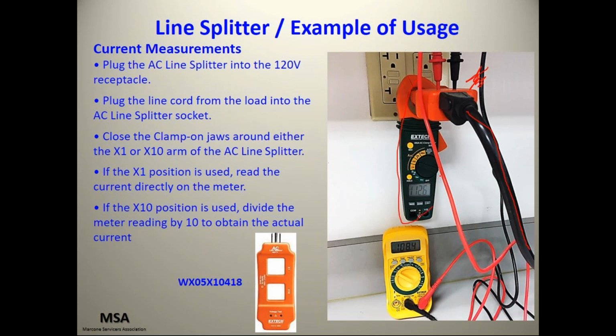Okay, they have the amp probe in the splitter. It says close the clamp-on jaws around either the X1 or the X10 arm of the AC line splitter. Okay, that's these openings here. If the X1 position is used, read the current directly on the meter. If the X10 position is used, divide the meter reading by 10 to obtain the actual current. The X10 is for reading very low current readings. If you're just reading microwave or any other appliance, you'll probably use the X1 position. And whatever you read, like say there, is what you're actually drawing.